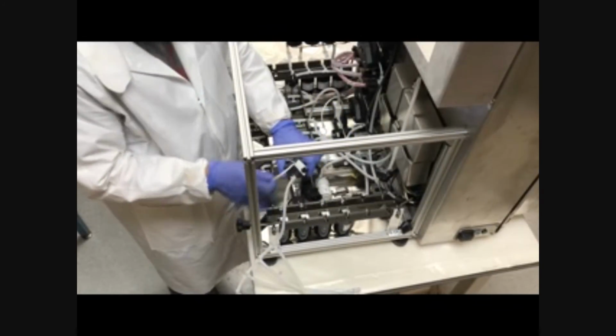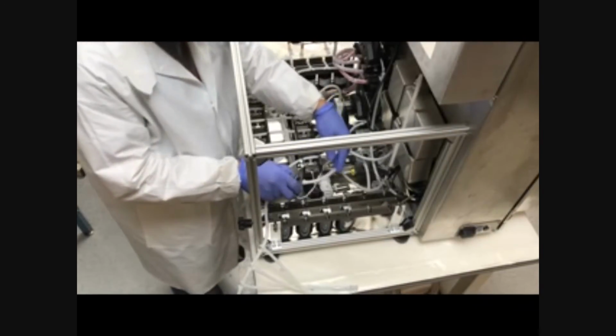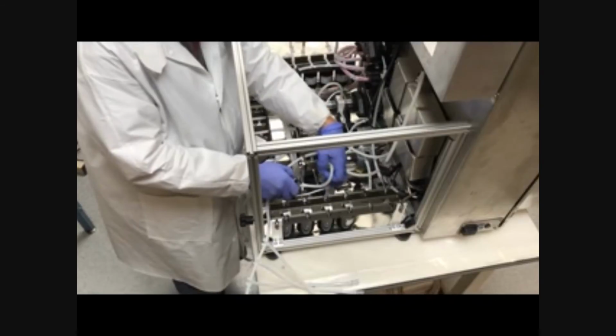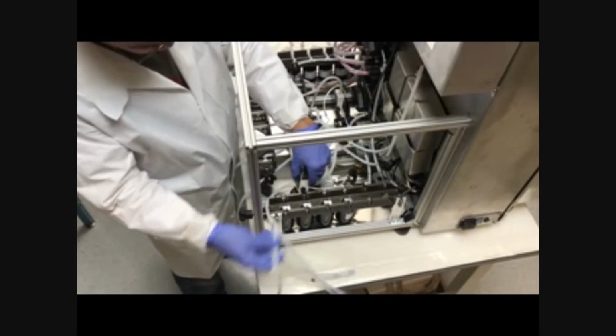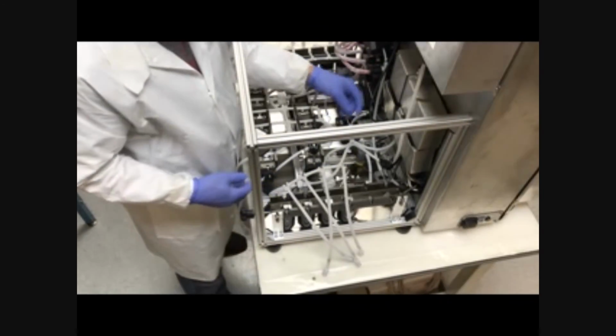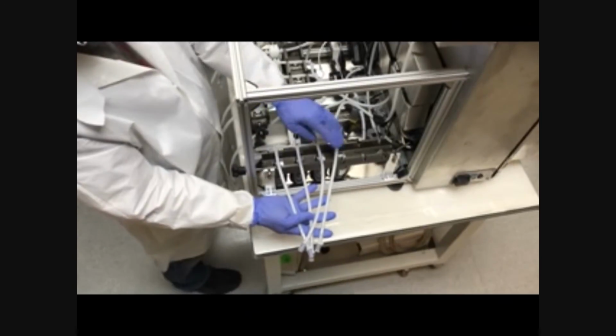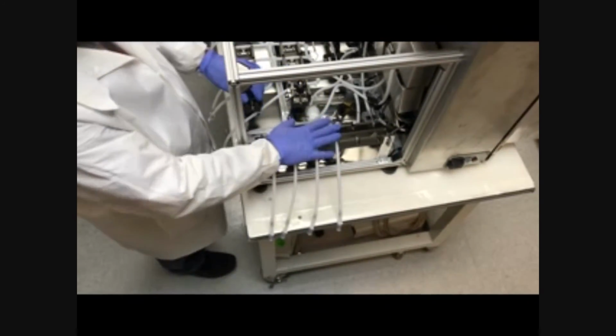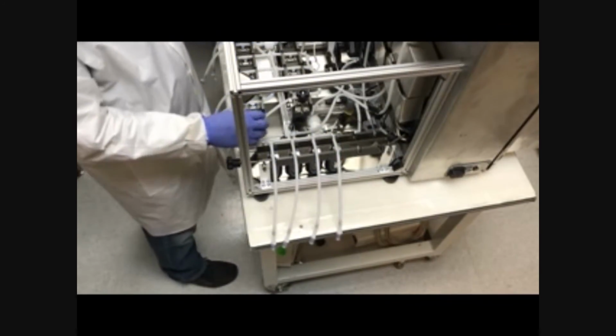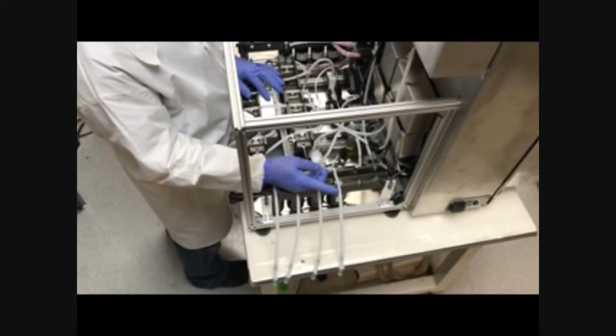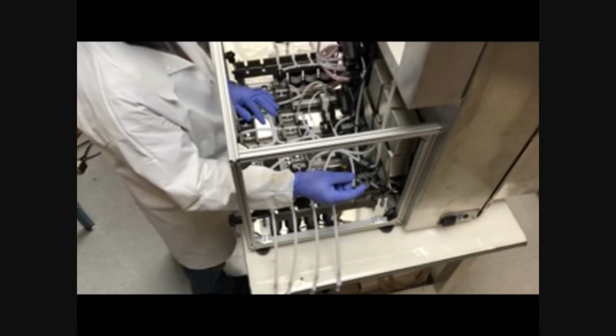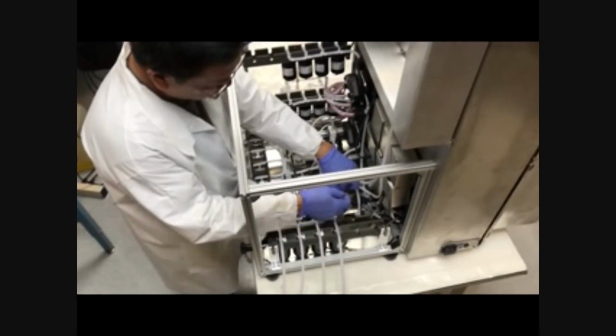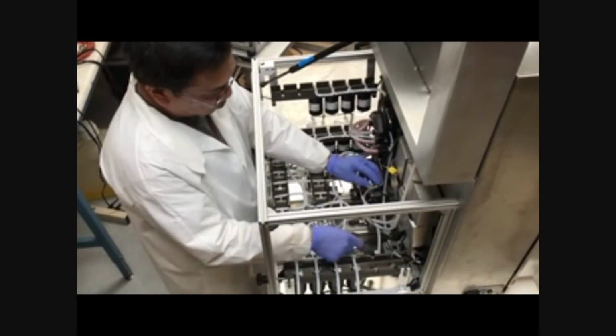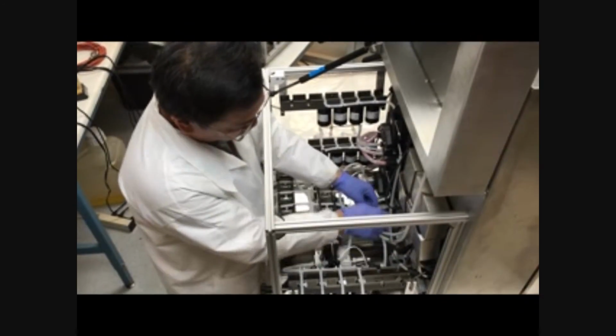There the clip is installed, and then he just sets it down on the bracket, which is below, so it snaps in. There. And then this is the fraction valve. So in this machine there are 4 fraction valves, and he lays the tubing down over the fraction valves. Right? So the entire flow path is now installed, and he's going to make the electrical connections next. The electrical connections for the pressure sensor, for the temperature sensor, and so forth. So that's the next step.